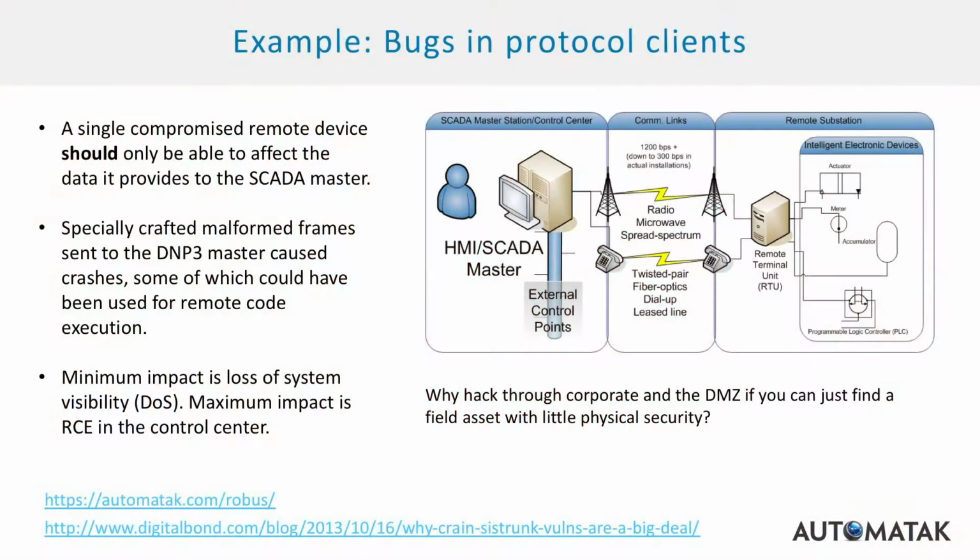So I'll give you one example of bugs that matter. Back in 2012, Chris Sistrunk and I were here at S4, and we were talking about bugs in SCADA masters, the communication servers that talk to many, many remote assets in the field, like remote terminal units or gateways and substations. Nowadays, they talk to lots of pole-mounted equipment like capacitor banks on lines or voltage regulators. And we found that there were quite a few bugs in the SCADA masters themselves. You could send intentionally malformed packets from the field back up to the master and crash the master system.